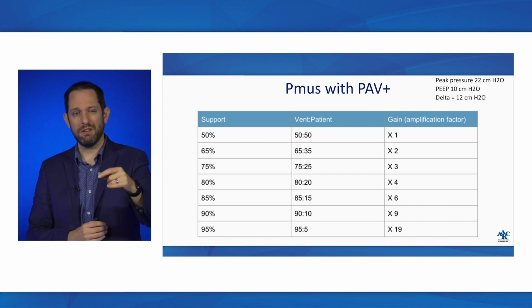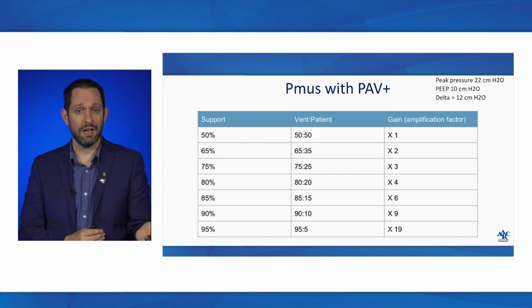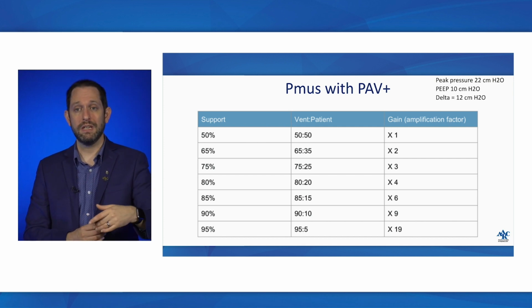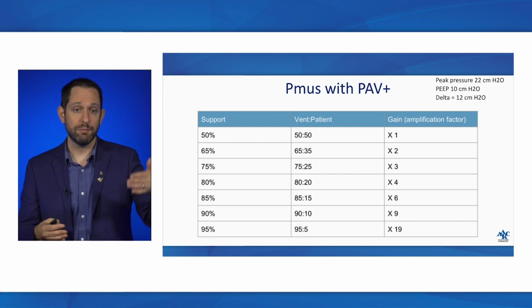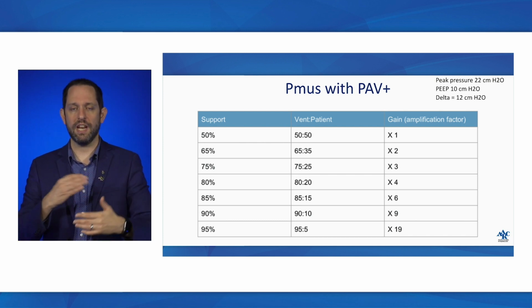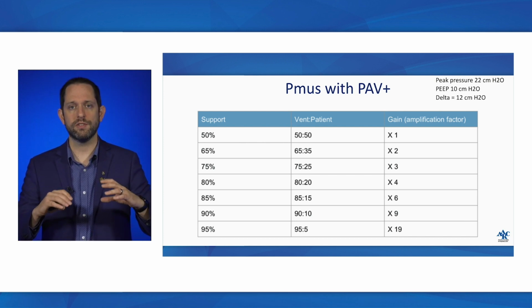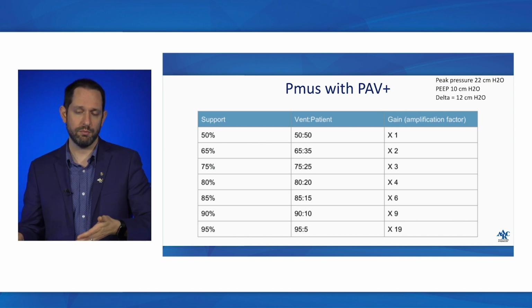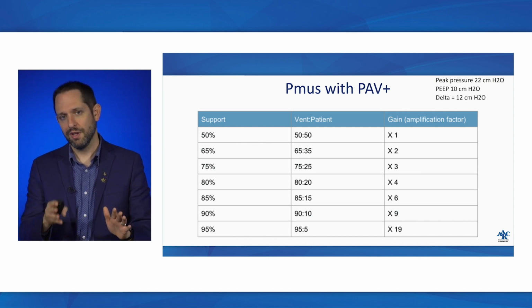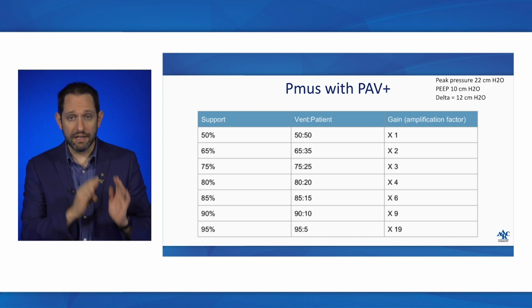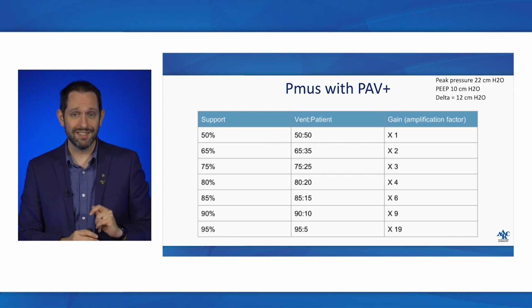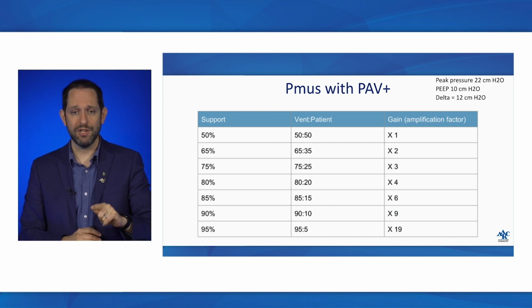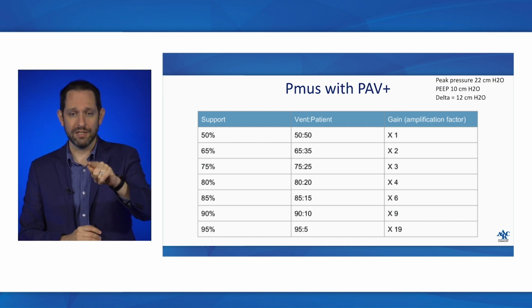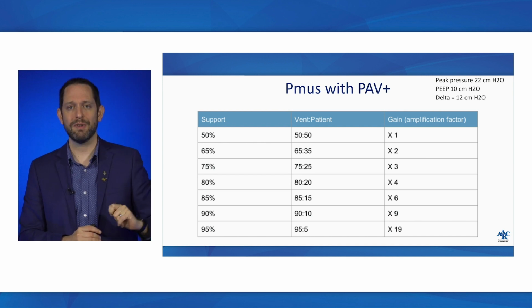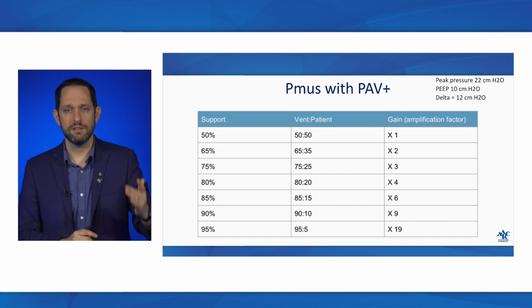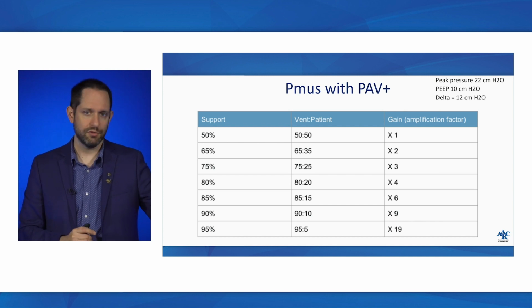So it's important that if you went from 50 to 55% on PAV+, you may not actually be assisting a whole lot more. Jumping from 50 to 65 will change that amplification factor by 1. You're now assisting 2 times as much as the work the patient's doing. Now, back to my example. At 12 centimeters of water that the ventilator's doing, if my setting was 65, I know that my patient is doing half of that because the ventilator's doing 2 times more than my patient. So what's my patient doing? 6 centimeters of water. 6 times 2 is 12.